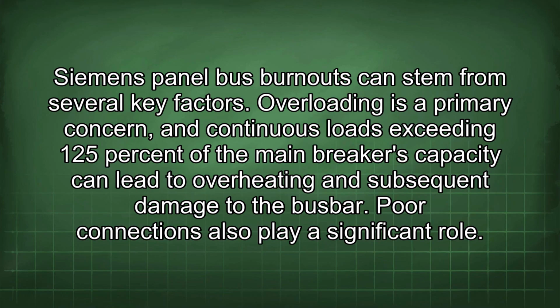Siemens panel bus burnouts can stem from several key factors. Overloading is a primary concern, and continuous loads exceeding 125% of the main breaker's capacity can lead to overheating and subsequent damage to the bus bar. Poor connections also play a significant role.